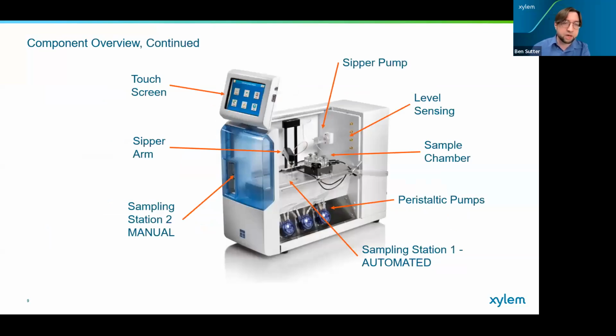Here's another view that's probably going to be the view you're going to be looking at most of the time when you're actually performing this service. The sipper pump is on the back wall there. You can see our level sensing hookups on the back wall there. We have our sample chamber, which we'll be doing a lot of work on, and our peristaltic pumps down below. Keep in mind that those colors are a little bit different than you may see on the peristaltic pumps from our live presentation, but they do exactly the same thing.